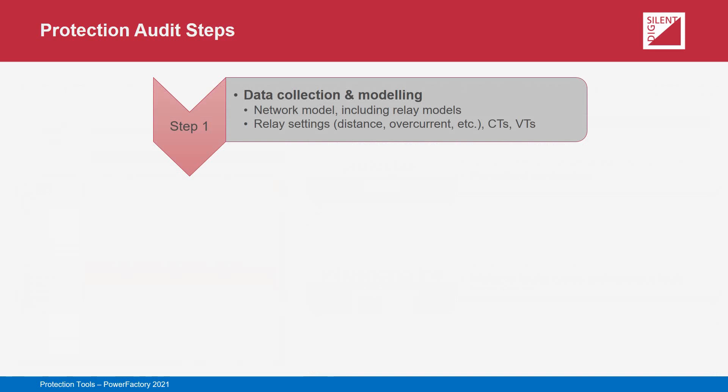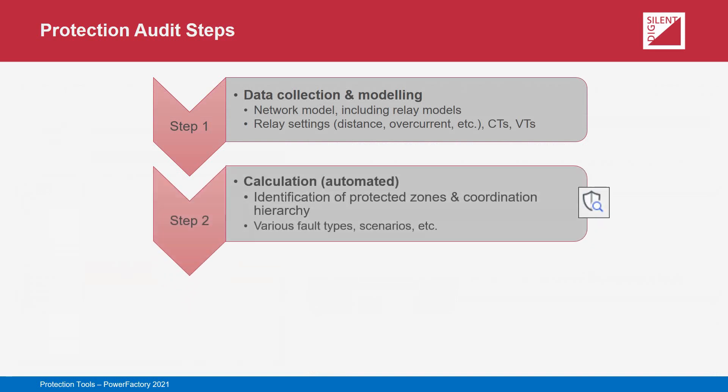At a high level, the protection audit process can be considered to consist of three main steps. The first step is to populate the PowerFactory model with the relays and settings which are going to be analysed. This will likely involve significant data gathering, where it is vital that the locations and models of relays, CTs and VTs are captured, and that their settings and ratios are identified. There may be scope to use the capabilities of DIgSILENT's protection setting database StationWare to help facilitate this. The second step is to carry out the automated calculations, during which the tool builds up a picture of the relationships between relay models and network elements being protected, as well as the coordination hierarchies between relay models.